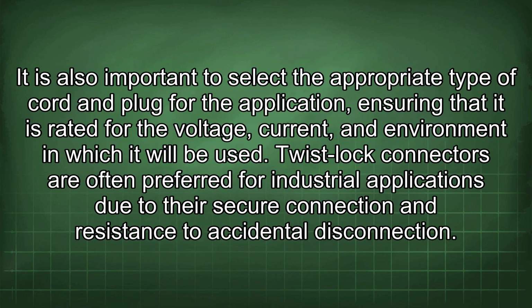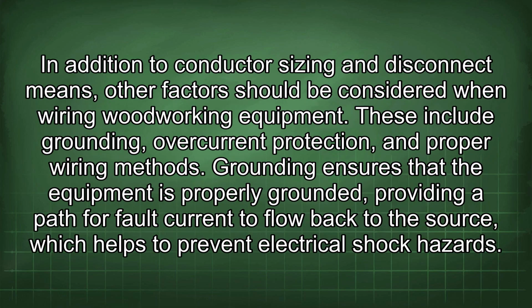It is also important to select the appropriate type of cord and plug for the application, ensuring that it is rated for the voltage, current, and environment in which it will be used. Twist lock connectors are often preferred for industrial applications due to their secure connection and resistance to accidental disconnection. In addition to conductor sizing and disconnect means, other factors should be considered when wiring woodworking equipment. These include grounding, overcurrent protection, and proper wiring methods.